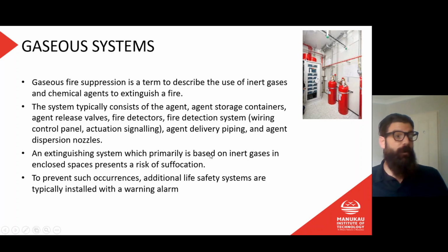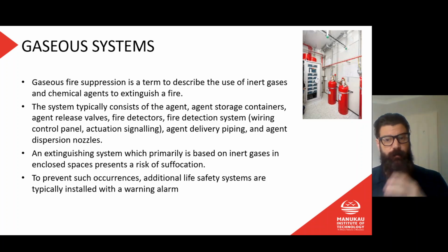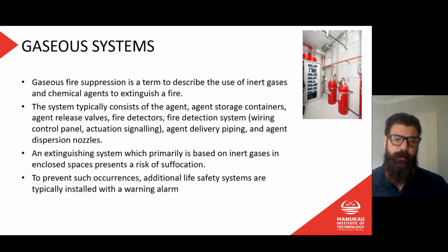And then we have gas systems. Gas fire suppression is a term to describe the use of inert gases and chemical agents to extinguish a fire. The system typically consists of the chemical agent, agent storage containers, agent release valves, fire detectors, a fire detection system, agent delivery piping, and agent dispersion nozzles. An extinguishing system based primarily on inert gases in enclosed spaces presents a risk of suffocation. To prevent such occurrences, additional life safety systems are typically installed with a warning alarm.